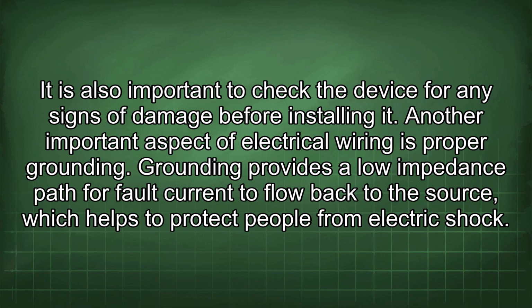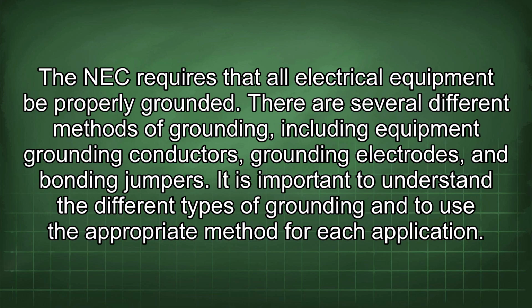Another important aspect of electrical wiring is proper grounding. Grounding provides a low impedance path for fault current to flow back to the source, which helps to protect people from electric shock. The NEC requires that all electrical equipment be properly grounded. There are several different methods of grounding, including equipment grounding conductors, grounding electrodes, and bonding jumpers. It is important to understand the different types of grounding and to use the appropriate method for each application.